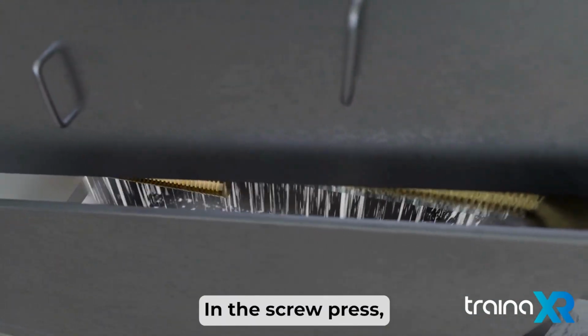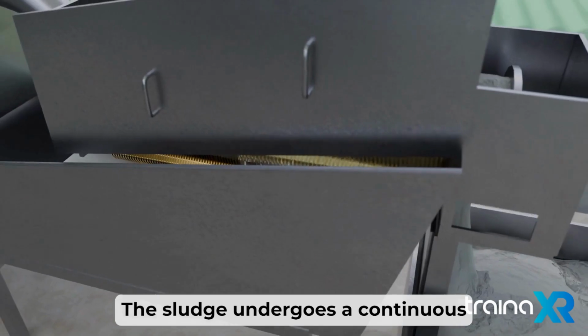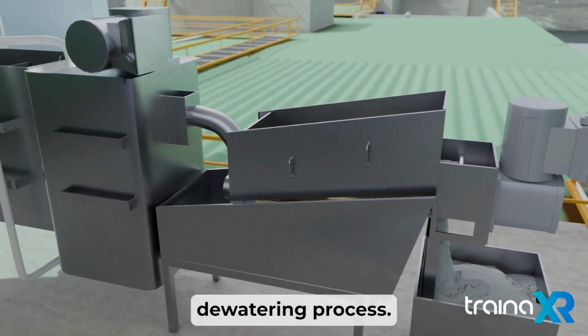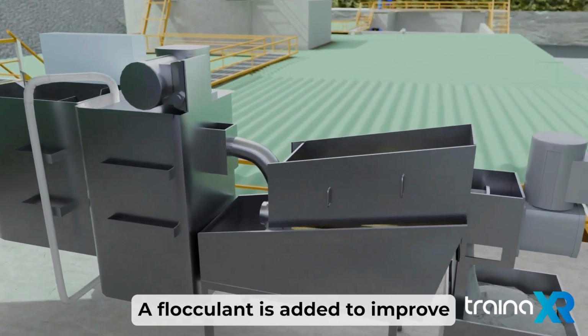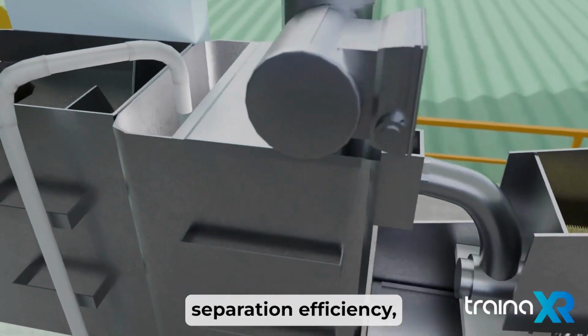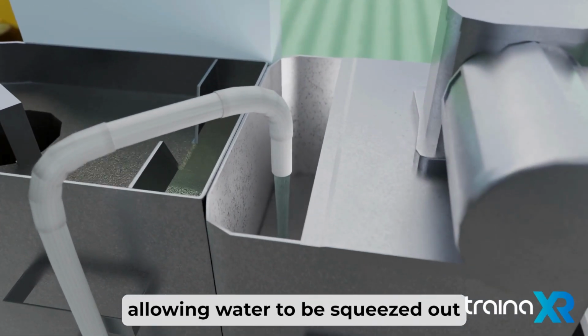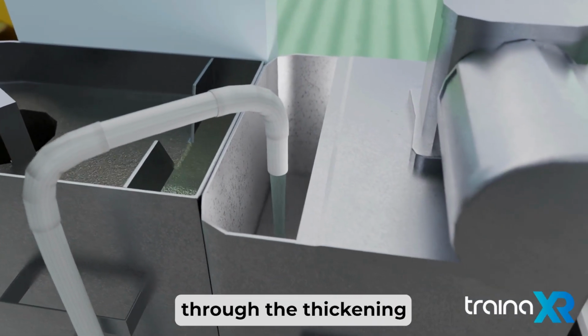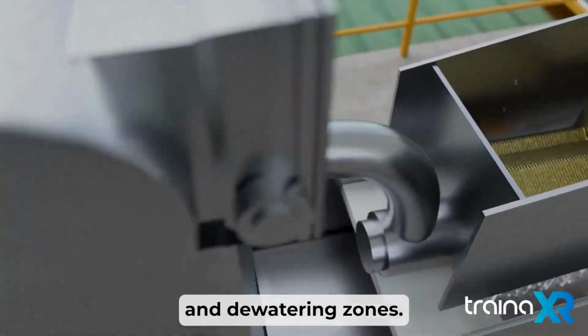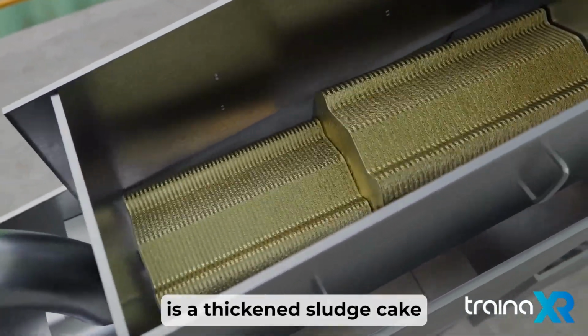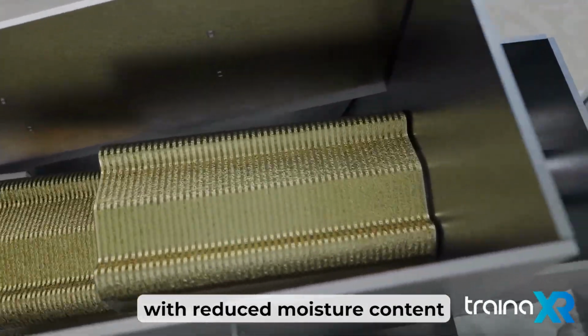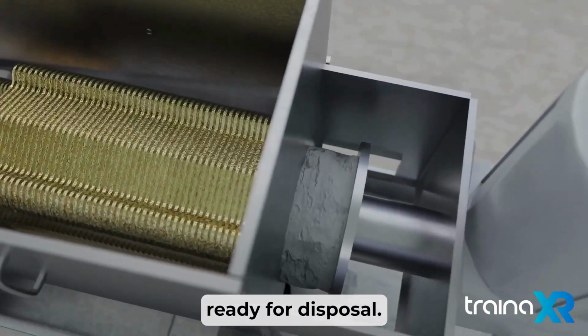In the screw press, the sludge undergoes a continuous dewatering process. A flocculant is added to improve separation efficiency, allowing water to be squeezed out as the sludge moves through the thickening and dewatering zones. The final output is a thickened sludge cake with reduced moisture content, ready for disposal.